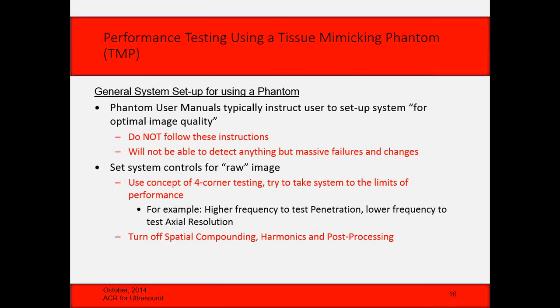So what I mean by that in this case is that if we're going to test penetration, we know that it improves if you go down in frequency. So when the sonographer needs to see deeper, they always lower the frequency they're scanning at. Well, since we're trying to push the system to the edge, we want to use the highest frequency for that probe when we're testing the penetration. And with axial resolution, we know as the frequency goes up, the axial resolution improves. So since, again, we're trying to stretch this to the limits, we're going to use the lowest frequency that probe will run at and test the axial resolution. And by doing that, we're much more likely to find problems. And then, as I mentioned, turn off harmonics, spatial compounding, and go to a single focal point.